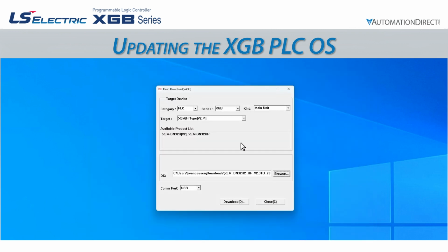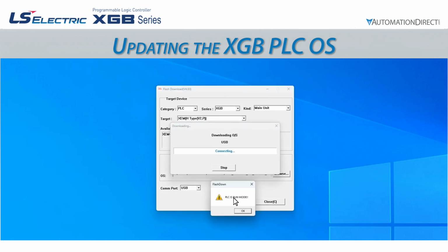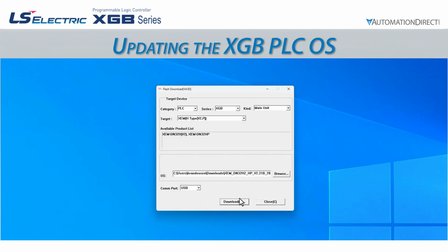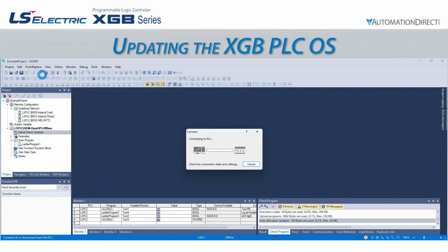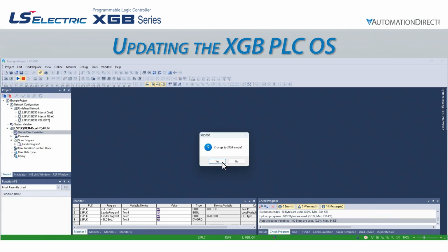We will connect to the CPU using USB, and the CPU must be in stop mode. It isn't possible to update the OS over Ethernet. Now that we have all of our fields set up correctly, are physically plugged into the CPU from our PC, and the CPU is in stop mode, we are ready to download.